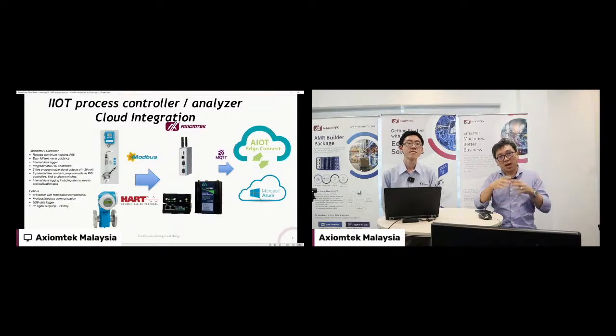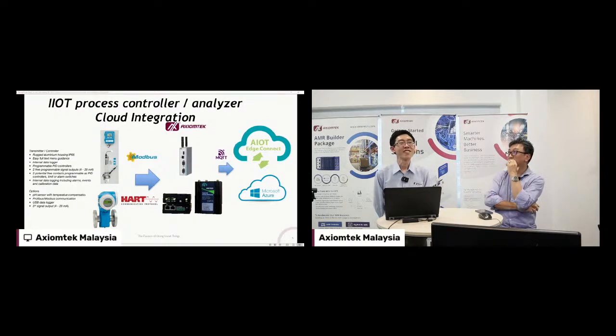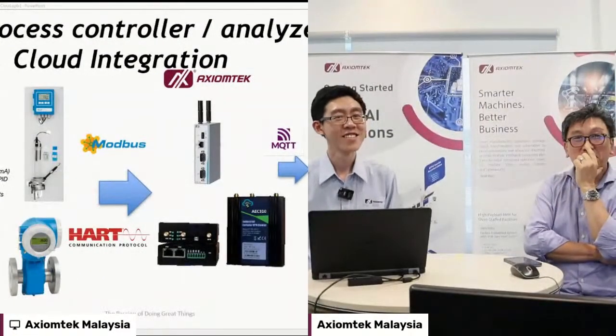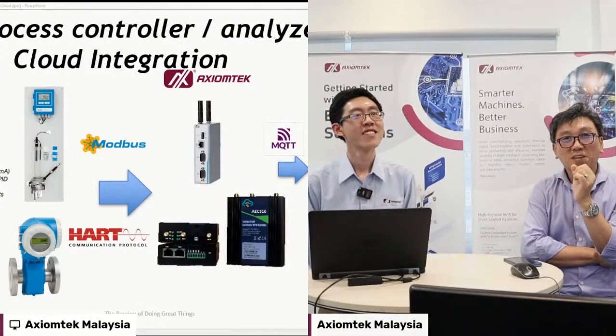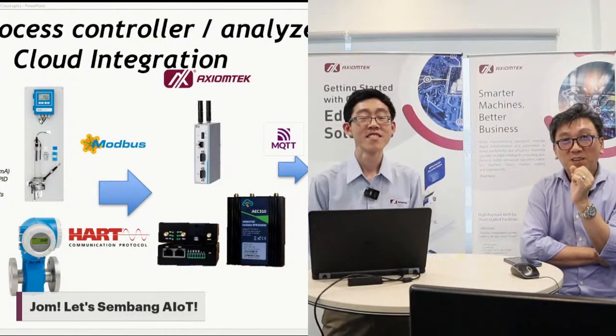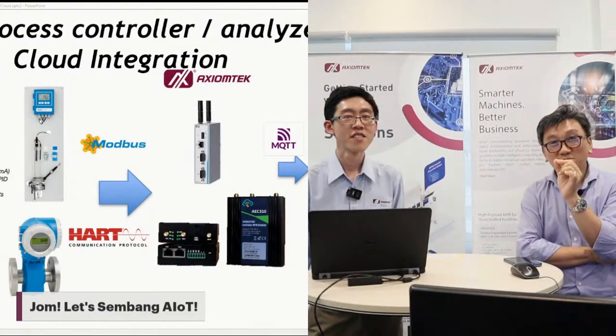This set of data can anytime be gathered by our IoT gateway or 4G gateway router and so on, doing some Modbus interface and so on. But one very interesting protocol is about HART. Do you know what HART is? HART is the name called Highway Addressable Remote Transducer. Highway, wow, highway must be very fast, high speed, it must be very high speed. But HART only talks 1.2K baud, 1.2K meaning 1200 bits per second.